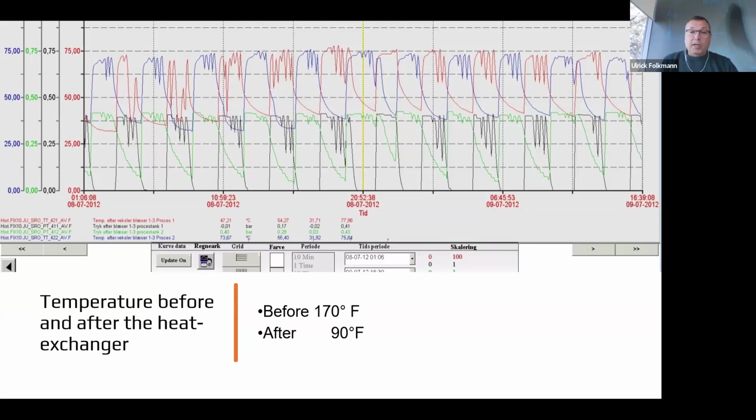Otherwise, you need to put a screen in front of the raw sewer before you go to the heat exchanger. But for the effluent, and it could also be for drinking water, or put it down in the concrete or in the sides of all the process tanks at the wastewater plant, it will be a very easy way to get a good, stable temperature into the heat pumps.